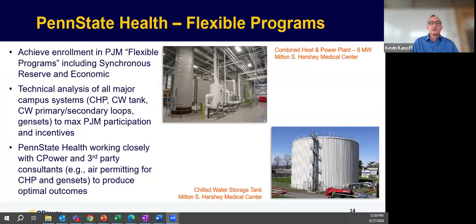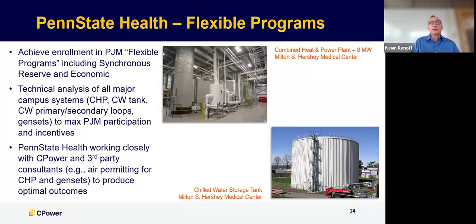But so far as our capacity management, we use a 1.4 million gallon chilled water storage tank, and when we flow at full capacity, we can drop a little under 2 megawatts with that, because we're pulling chillers back. Our chillers are reducing their output as we switch over to the chilled water storage tank. Additionally, because we're a large facility with a large building automation system, we have significant common areas that are not critical areas. So we have a button within the BAS that our operators push, and that gives us another megawatt or so of demand reduction. So those two are the primary ways that we've been reducing our capacity.